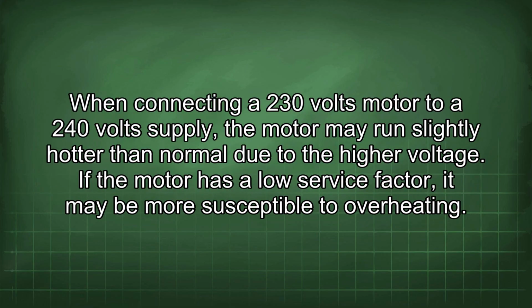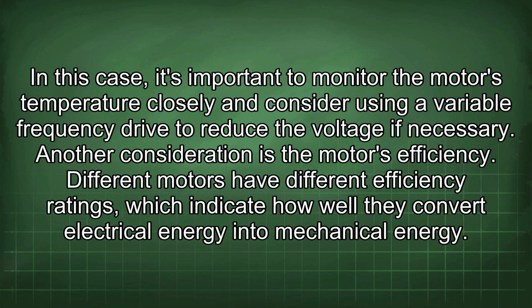When connecting a 230 volts motor to a 240 volts supply, the motor may run slightly hotter than normal due to the higher voltage. If the motor has a low service factor, it may be more susceptible to overheating. In this case, it's important to monitor the motor's temperature closely and consider using a variable frequency drive to reduce the voltage if necessary.